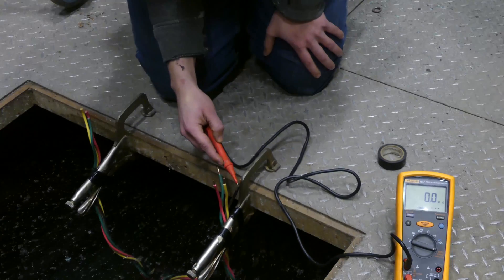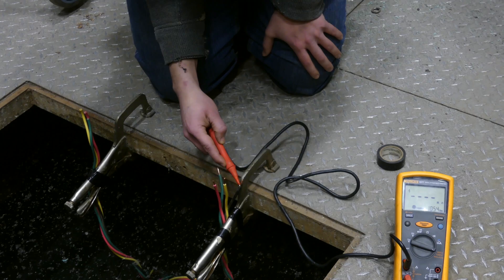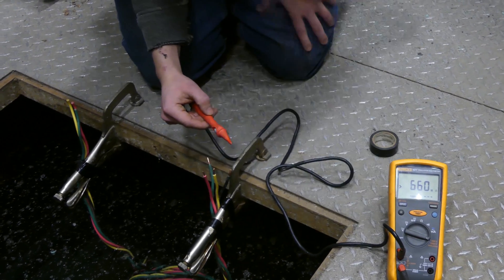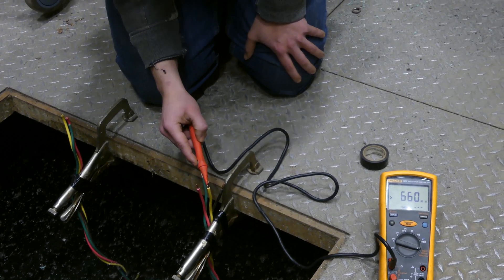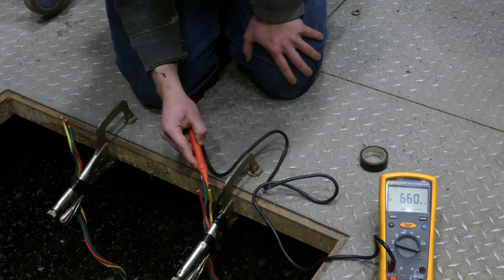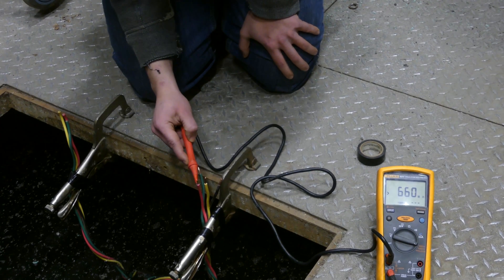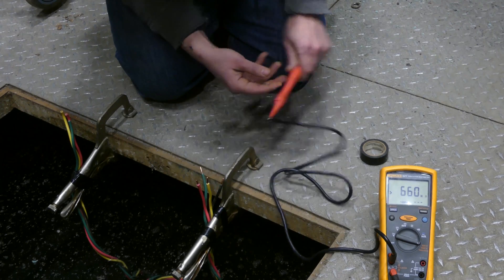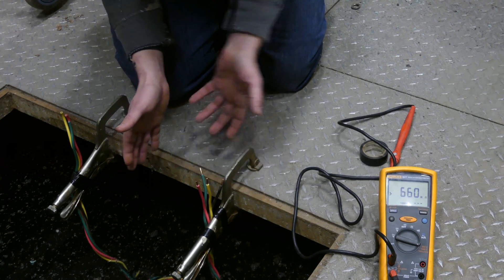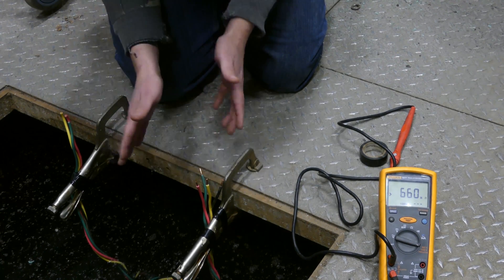But anyways, let's go ahead and test one of these. So we'll test the black here. And we get 660. So that's actually 660 million ohms of resistance. So that is definitely perfect wire. 660 again on the yellow and 660 again on the red. So what I've just shown you is a wire test that we have perfectly good wire.